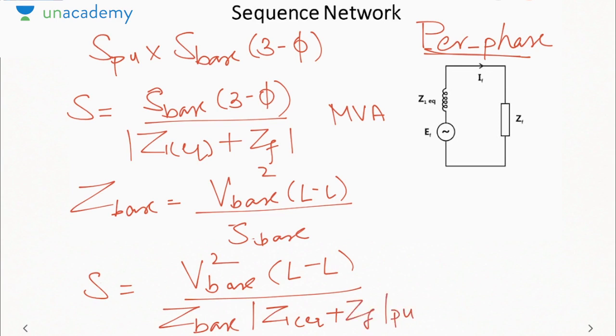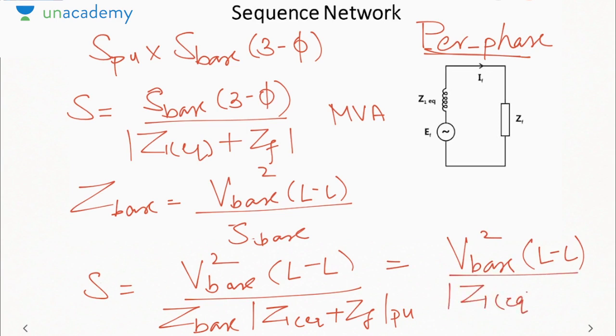Now when base impedance is multiplied by PU impedance, we get the actual impedance. So it is V base square line to line by mod Z1 equivalent plus ZF. So this will be the short circuit MVA, or the power delivered to the short circuit for a triple L fault or line to line to line fault. This is your actual value MVA. In per unit value it is 1 upon Z1 equivalent plus ZF in PU. So that is how to derive the short circuit MVA.